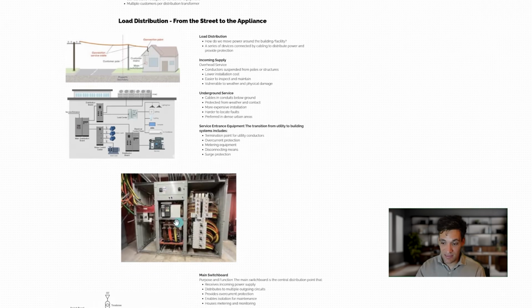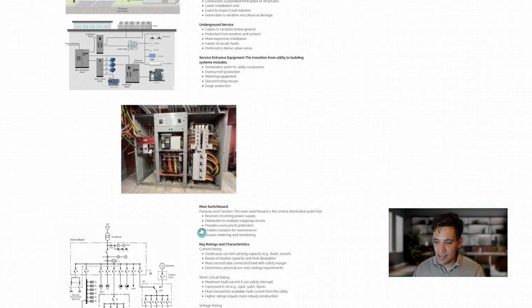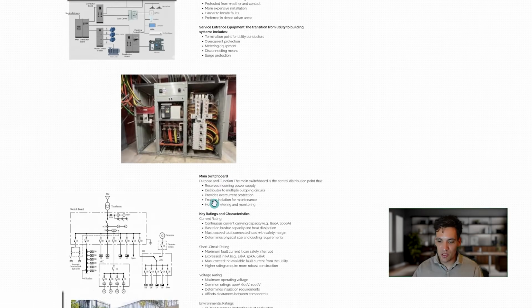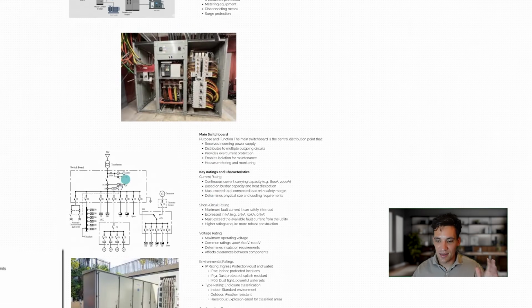So if we look at this larger facility, this is some sort of industrial facility. You can see the incoming cables are these larger cables here, while the outgoing cables that spread the load through the facility are here. Within this board, there'll be some metering and a circuit breaker that protects the incoming cable. So on a large facility, this is the main switchboard. On your house, you wouldn't really call it a main switchboard, but you might just call it a distribution board. Basically, the main switchboard is where the incoming power comes in, and then it is connected to all of the outgoing circuits that spread the load through the facilities.